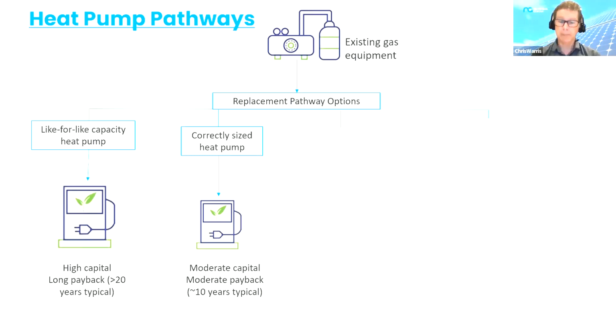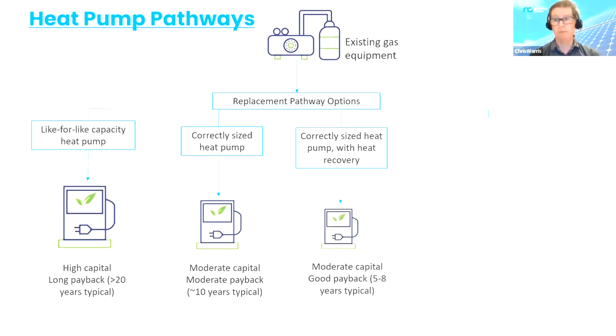So if you look at the heat load properly, either model it or look at the actual data from your existing heating plant, and then correctly size the heat pump to meet that demand, you can often put in a much smaller one, sometimes half the size. And that'll give you a much better payback. It'll reduce the capital and improve the payback. 10 years is typical of what we see from that, as opposed to often over 20 years if you're doing a like-for-like replacement. The other thing you can do to improve the performance and reduce the size needed for your heat pump is to try and do some heat recovery.